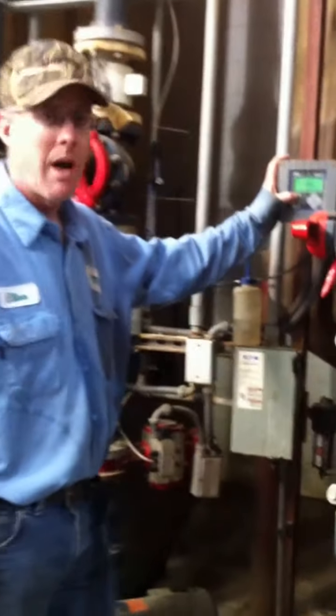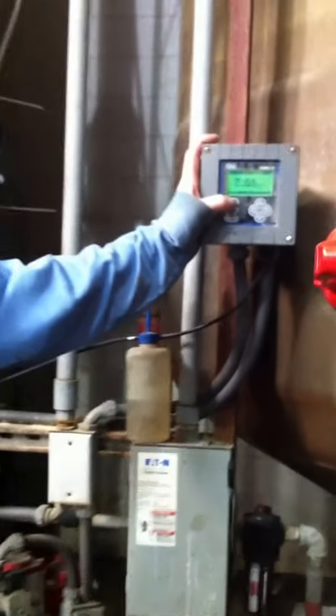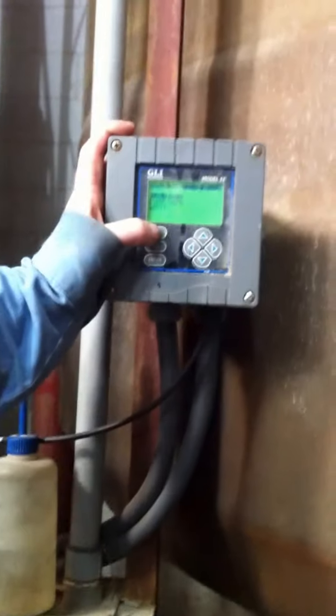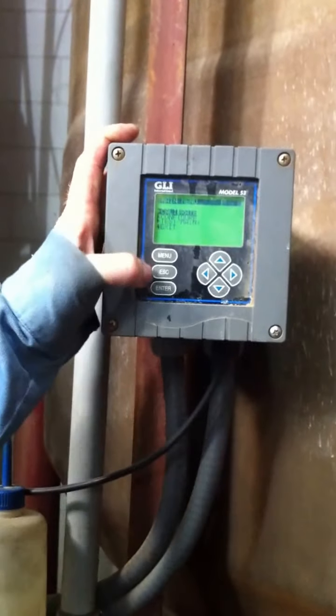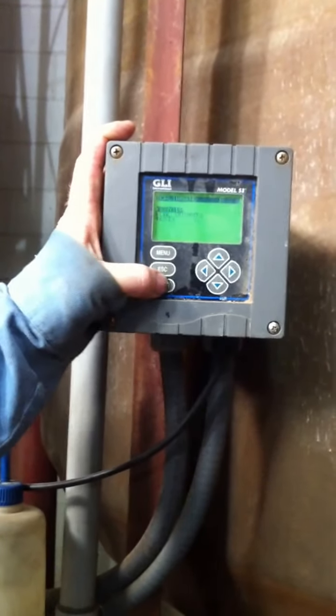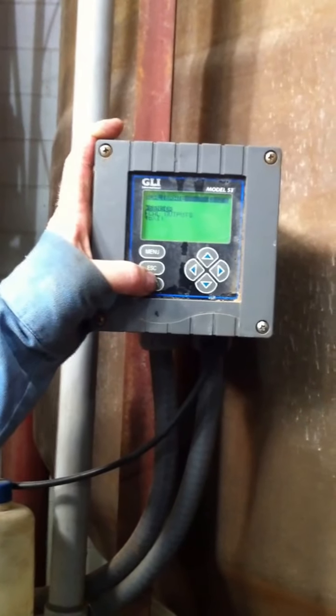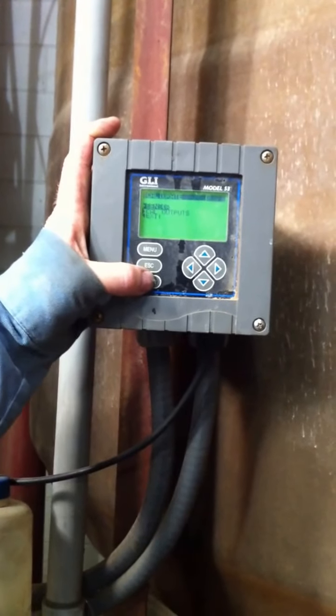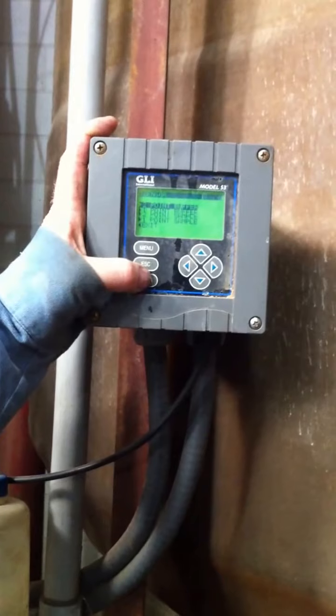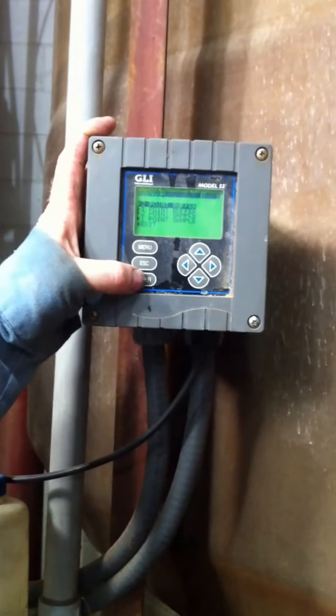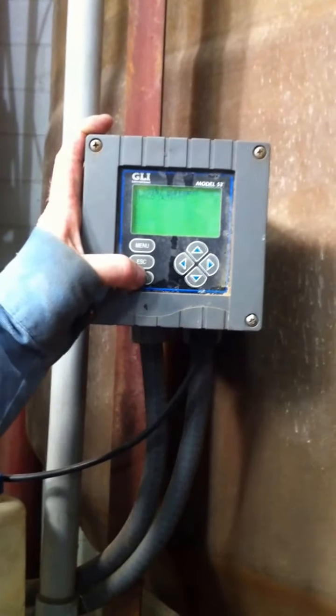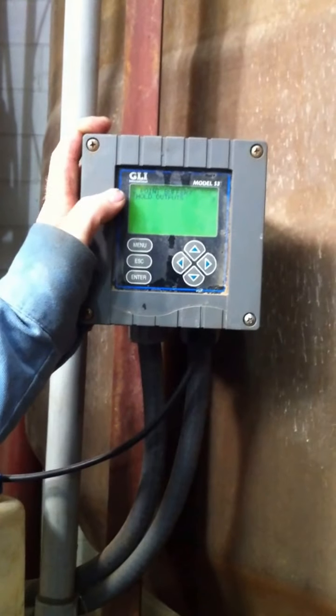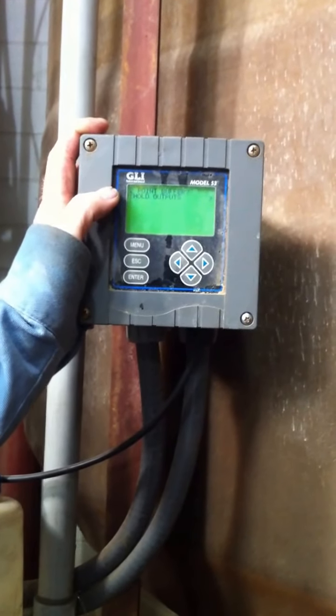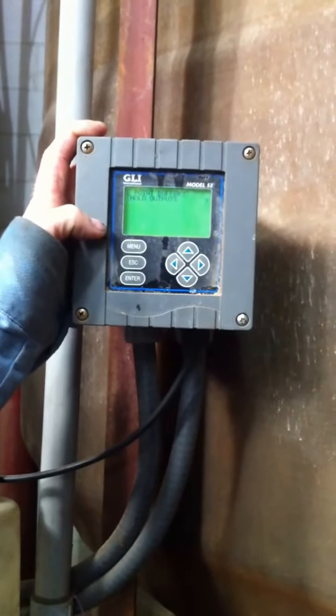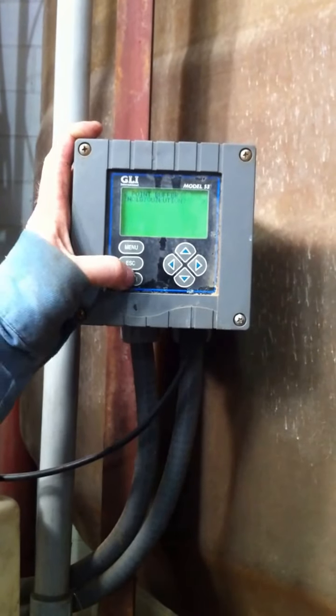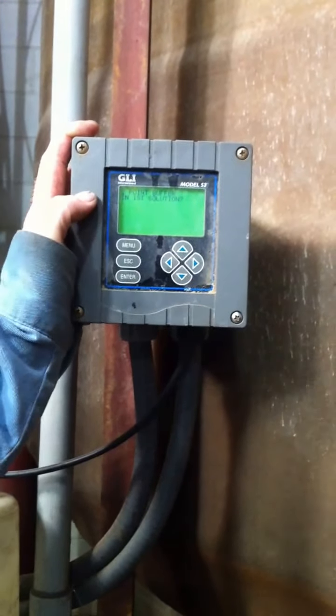You'll hit the menu option on the controller. That will bring you into a main menu. We're on calibrate here. We'll select calibration. We want to calibrate the sensor, so we'll enter sensor there. We'll select 2-point buffer and we'll push enter here. And then when you're in operation, you'll want to hold your outputs on your controller.